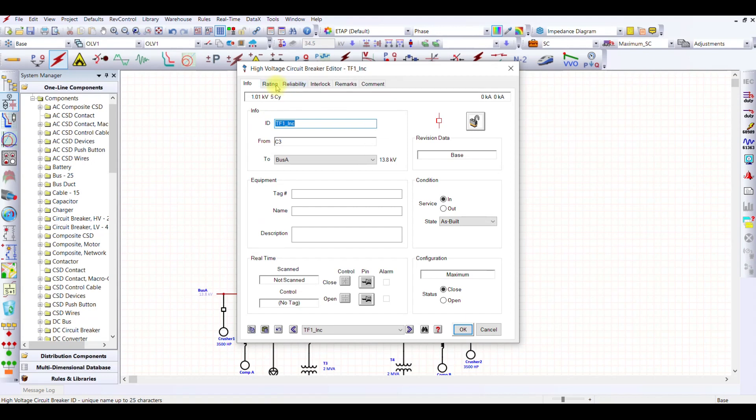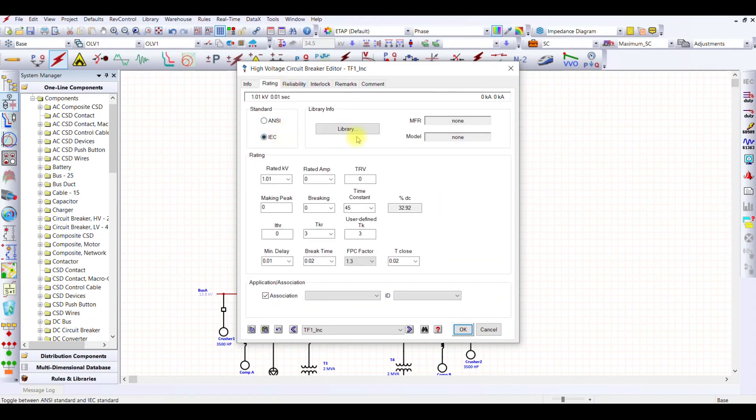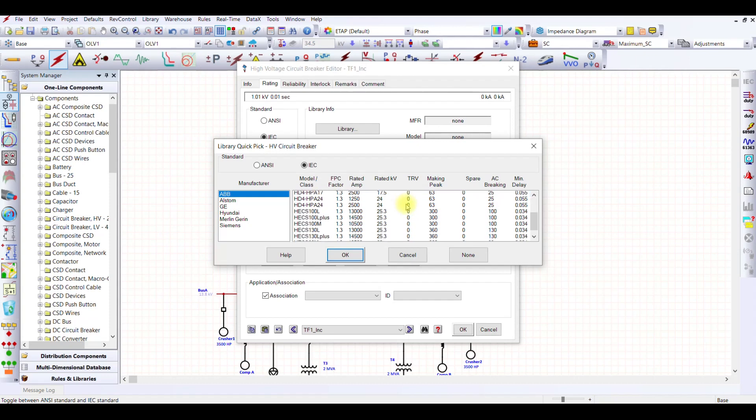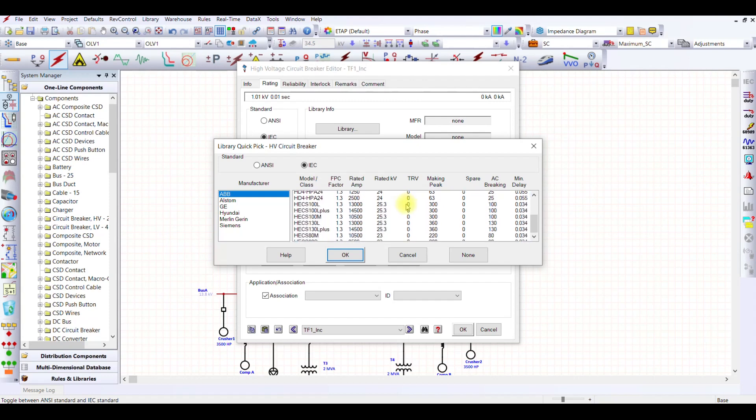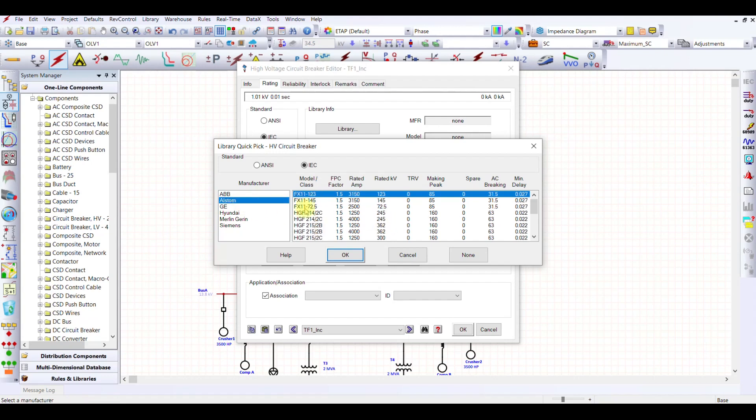IEC standard, I go to library. Let's select some ABB breaker. I can use, so I have 13.8. I can use my switchgear. I can select 15 kV rated, but 15 kV will work for me. 13 won't work because it is less. I can work with 17.5. Let's see what we have in Alstom.